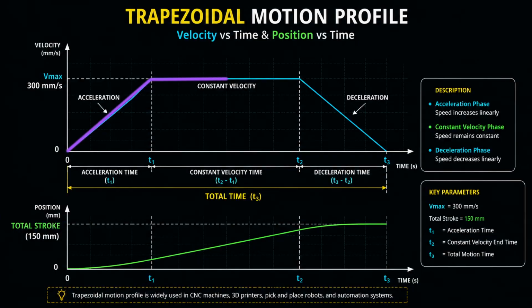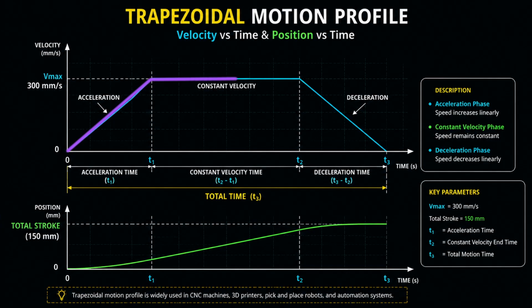Let's understand how the laser head moves. A servo control axis follows a motion profile: acceleration, constant speed, deceleration, and stop. You can see this graph. On the bottom there is time and on the left-hand side there is speed, and these two lines determine acceleration and deceleration. Every servo motor follows this motion profile. During acceleration, the motor produces its highest torque. During constant speed, the required torque is much lower.